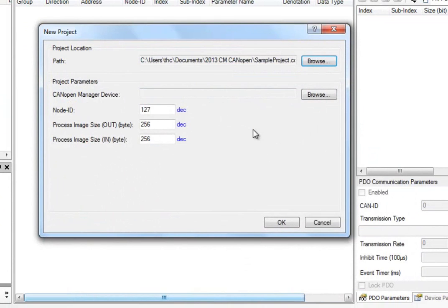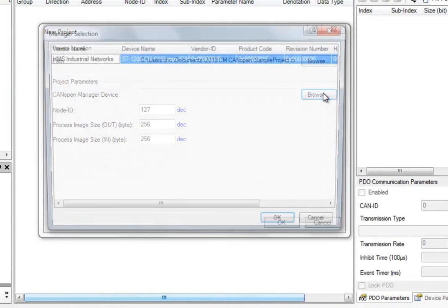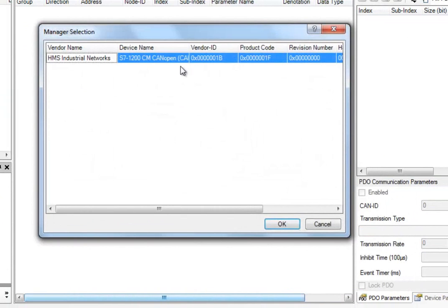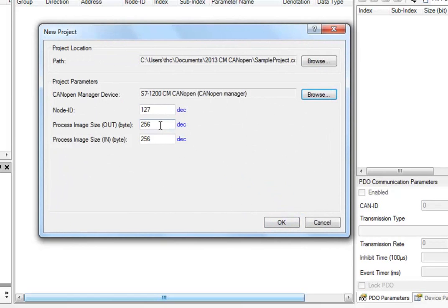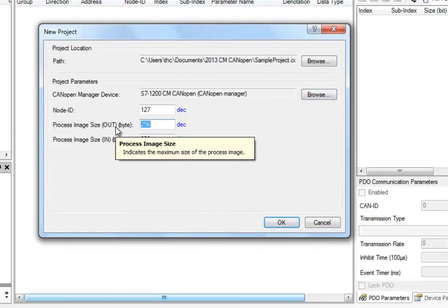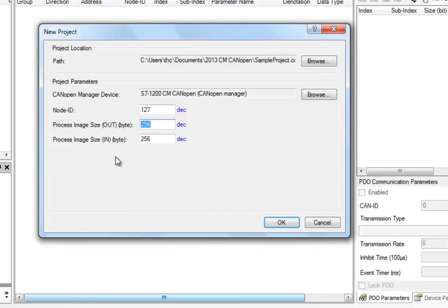I then need to specify what type of manager device I am using. I select Browse and choose the S7-1200 CM CANOPEN. I also need to specify the node ID of the manager device. I let this remain at 127. We also need to choose how many bytes to send to and from the manager. Since we only have 8 bytes in and 8 bytes out in this configuration, I change the process image to 8 bytes out and in. The process image is the buffer where the data is stored in the manager and can be up to 256 bytes in each direction.